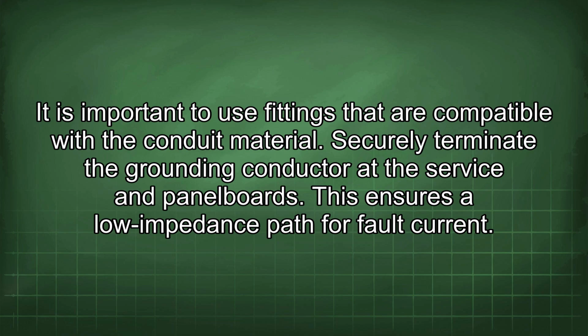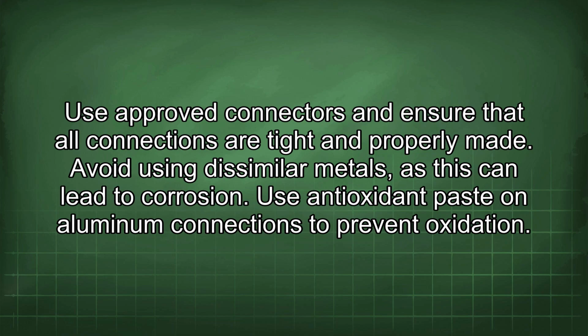Securely terminate the grounding conductor at the service and panel boards. This ensures a low impedance path for fault current. Use approved connectors and ensure that all connections are tight and properly made. Avoid using dissimilar metals, as this can lead to corrosion. Use antioxidant paste on aluminum connections to prevent oxidation.